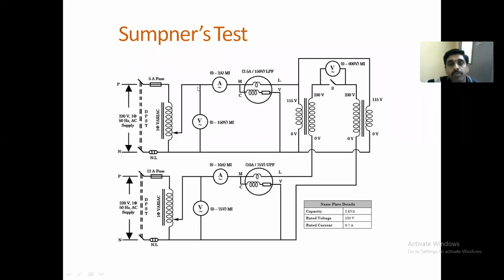Here you can see the testing setup with all the ratings. It is an actual laboratory setup. Here two transformers are there. The primaries of the transformers are connected in parallel to the supply, and the secondaries of the transformers are connected in series. You can observe these two are primaries, connected in parallel to the supply, and these two are secondaries, connected in series.